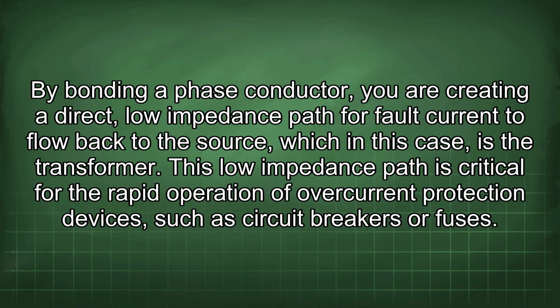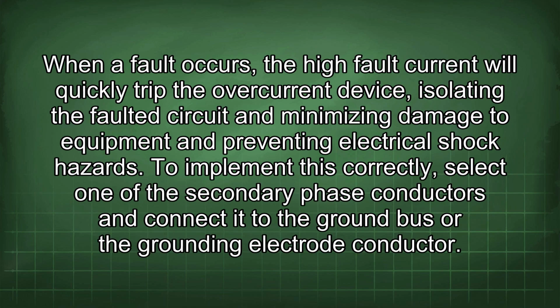By bonding a phase conductor, you are creating a direct, low impedance path for fault current to flow back to the source, which in this case is the transformer. This low impedance path is critical for the rapid operation of overcurrent protection devices, such as circuit breakers or fuses. When a fault occurs, the high fault current will quickly trip the overcurrent device, isolating the faulted circuit and minimizing damage to equipment and preventing electrical shock hazards.